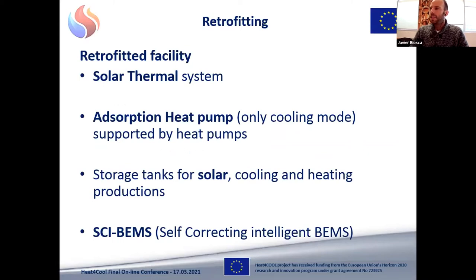The retrofitted facility consists in a solar thermal system coupled with an absorption heat pump, which only works in cooling mode. And these generation systems are supported by the old heat pumps. There are also storage tanks for the storage of the solar cooling and heating productions. And the retrofitting also comprises the implementation of the SCI BEMS. This is the self-correcting intelligent building energy management system.